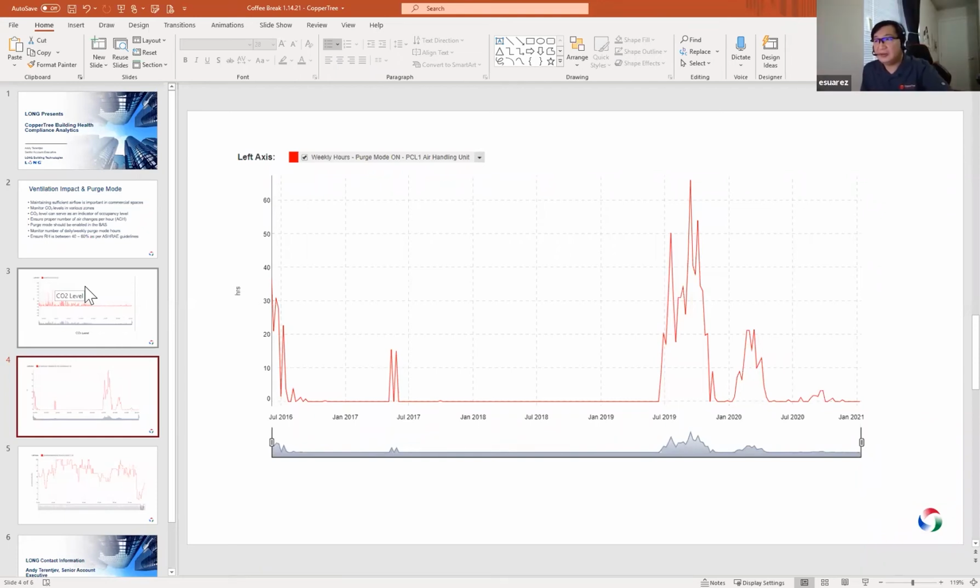On the other hand, being able to track historical data of what has gone on for the last week, the last month, or even the last year, unfortunately, unless you have a data repository for your trend logs within the BAS, typically the memory only allows you to store trend log data for a few days. And then you have to offload that into a separate repository. Depending on which BAS you're using, either you have historians or you're using some form of cloud storage.